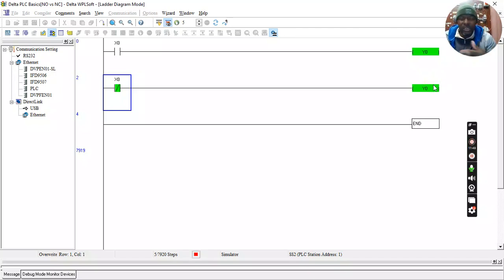There are so many PLCs. You will see some PLCs won't allow this. But okay, fine. This one allows it. Let's see the difference here. This instruction here is saying that line should be broken, so there should be no power for Y0. But because a conflicting instruction is saying power to Y0, because it's saying I'm closed here, even the line that would normally be off is now energized, because this and that is the same thing. If it gets power and it's the same thing, that one will have power. So you can see already that it does not make sense.